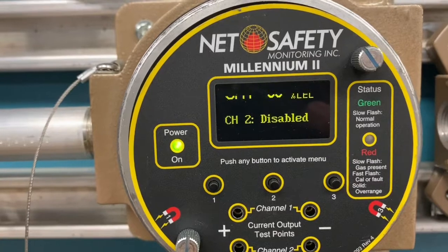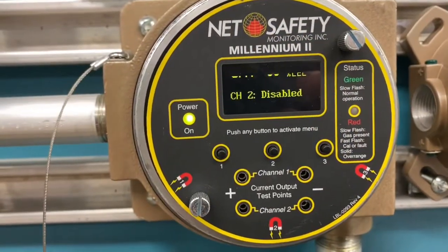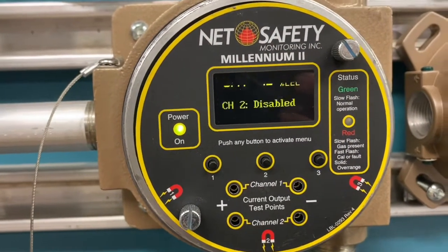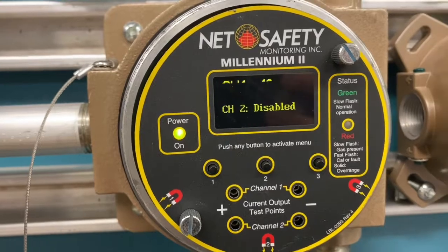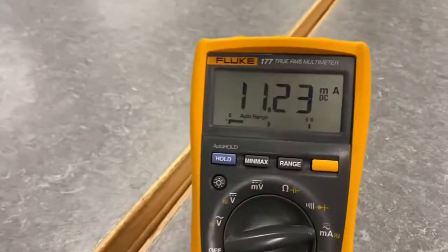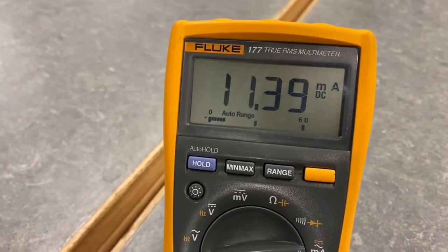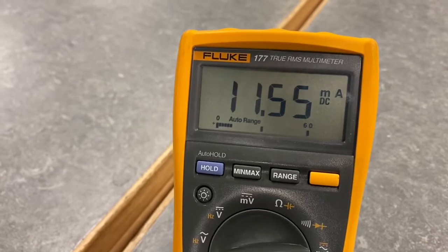We'll just see if it reads correctly. Get it up to 50% LEL and we'll check. This should be reading 50% span gas here. We're climbing, making our way up to 50% LEL. And if we look down here, our milliamps are getting up close to 12, which would be 50% between 4 and 20.